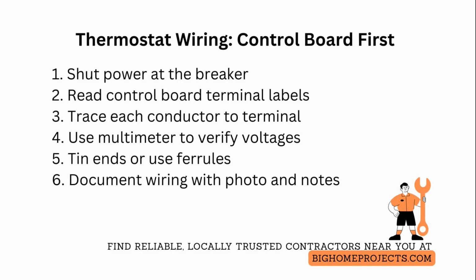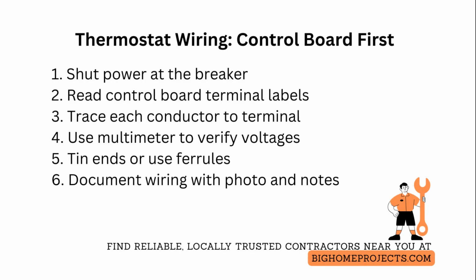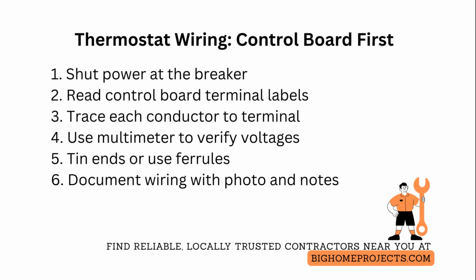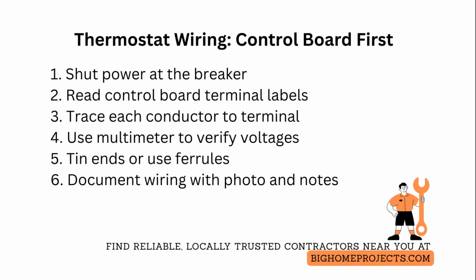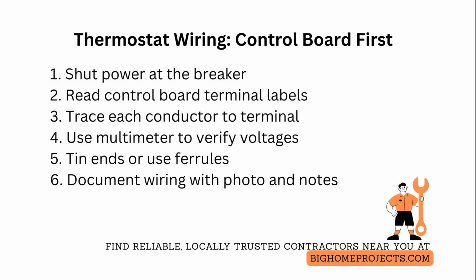Replace any corroded terminal blocks and check for loose spade connectors on relay outputs. These cause intermittent calls that look like thermostat failures but are actually control board reliability issues. Always resecure the service panel. Restore power and perform a full thermostat commissioning. Call for heat and cooling. Verify fan operation and watch for the correct relay clicks and voltage changes at the board as the thermostat changes state.